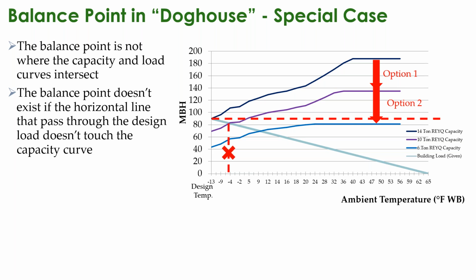that curve. Now you still have your entire load that needs to be covered, and we're assuming that your entire load is going to be covered by that equipment because the doghouse is maintaining a temperature that system is able to provide that capacity you need to meet your load. If your capacity curve, as in this case, the 6-ton is below that correlating line, then you do not have a balance point with that piece of equipment. So you would need to look at something between a 6 and a 10-ton. Most manufacturers have an 8-ton. That might be a fit here. And that's where you have to refer to the manufacturer's design guides and engineering manuals to get this data.